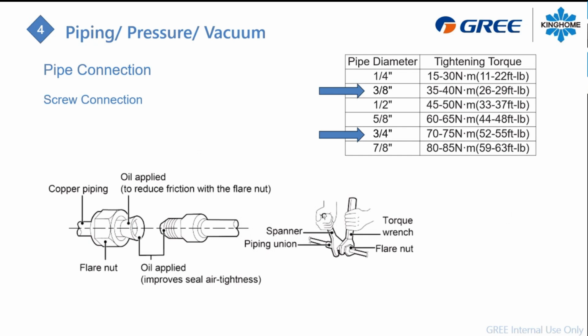So make sure you make a good flare connection. To make it, you can apply some compressor oil or vacuum oil around the outside section of the flare, just to remove the friction. So when you use your torque wrench and another wrench or spanner to hold the second part of the piping, you don't want it to twist on the flare. You need to make a smooth connection, like it will be very compressed, very hard.